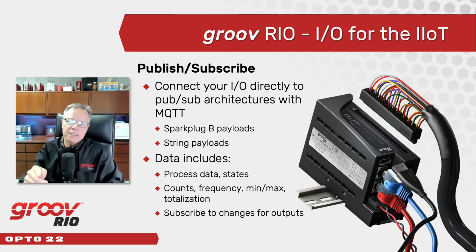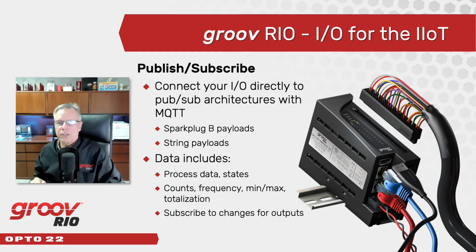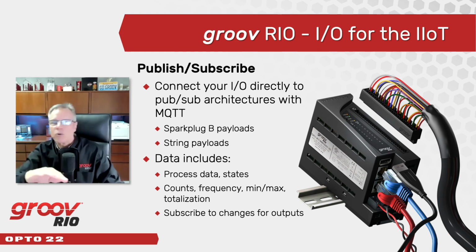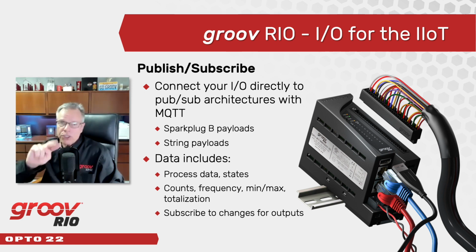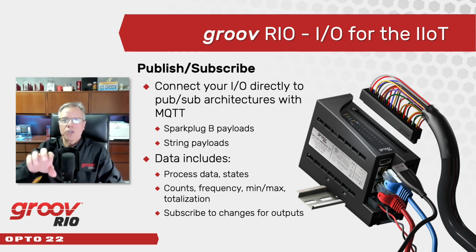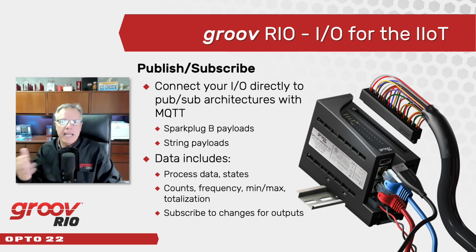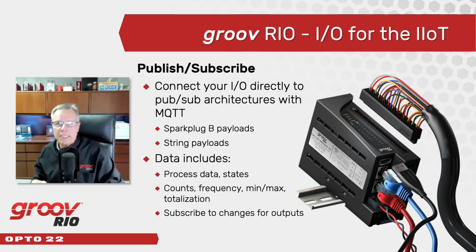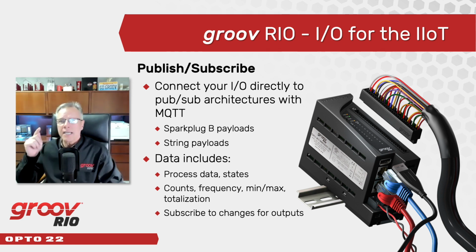So let's cover the MQTT publish subscribe capability that I briefly mentioned earlier. RIO has built-in support for configuring and publishing your I/O data directly to any MQTT broker with two choices in payload. Our favorite is the open source payload and topic namespace definition called Sparkplug B, which is also natively supported by Ignition and Canary Labs. But we also support simple string payloads for those just dabbling in MQTT and smaller non-critical applications. No worries, your choice. But rather than just publish process data and discrete states, we can also publish metadata about the I/O as well, including counts, min-max values, and more. You'll see all this firsthand in the live demo.